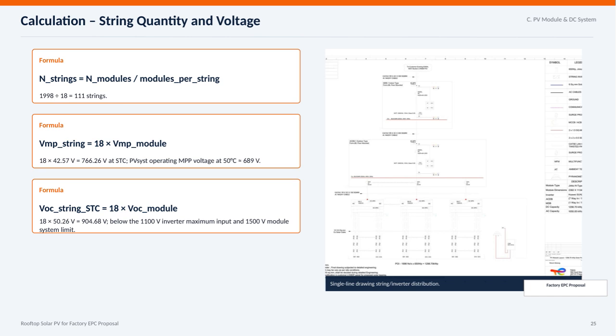Next, the open circuit voltage, VOC, is calculated by multiplying 18 modules by the VOC of each module, 50.26 volts, totaling 904.68 volts. This value is safely under the inverter's maximum input voltage of 1100 volts and the system's 1500 volt limit, ensuring safe operation. This calculation is crucial to correctly design the string and inverter configuration for the system. Understanding these voltage limits guarantees system safety and efficiency.